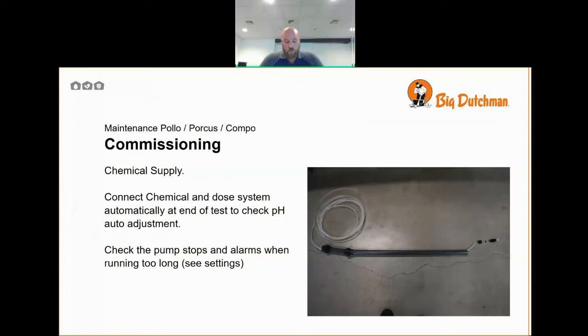Connect the chemical dose system, set it to automatic at the end of the test and at the end of the commissioning, and ensure that the pH automatically adjusts. Check the pump stops when alarms are triggered and when it's been running too long. See the settings for further information.